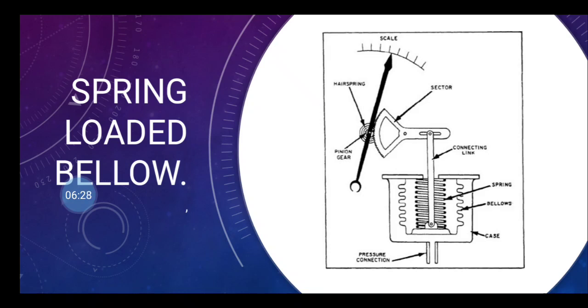Material for bellows: which materials are used? Phosphor bronze is used in the bellows. The spring is made of heat treated steel.